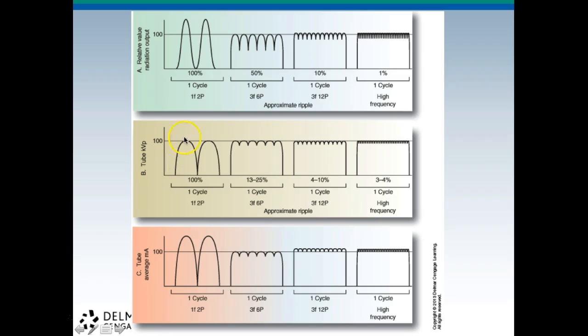This is tube kVp, so you can see here we're at 100% ripple, and with a 3 phase 6 pulse, we're at a 13 to 25% ripple. And with our 3 phase 12 pulse, we're at a 4 to 10% ripple, and with high frequency, we're at a 3 to 4% ripple. And then here with our tube average mA, we have 1 phase 2 pulse, a 3 phase 6 pulse here, and a 3 phase 12 pulse with the high frequency. So as you can see, our goal is to hit the high frequency. When I started in X-ray, I was working on a 3 phase 6 pulse, so it changed our technique quite a bit. We had to adjust as we went to the high frequency generators.